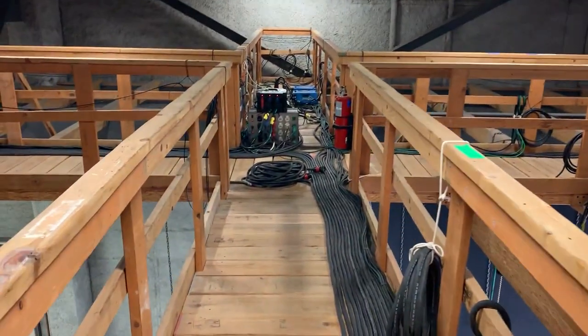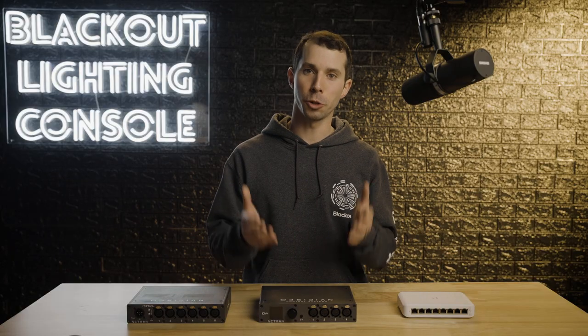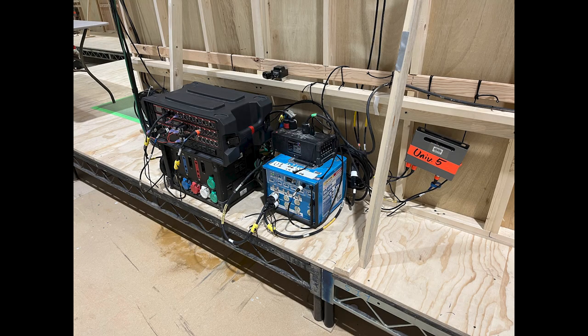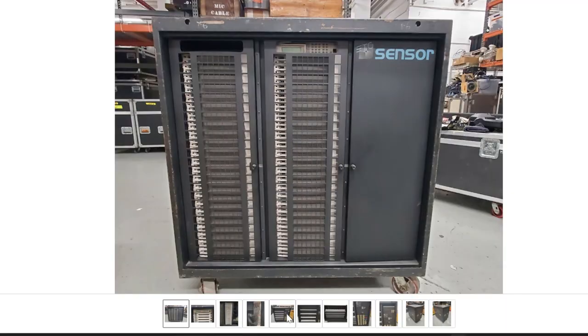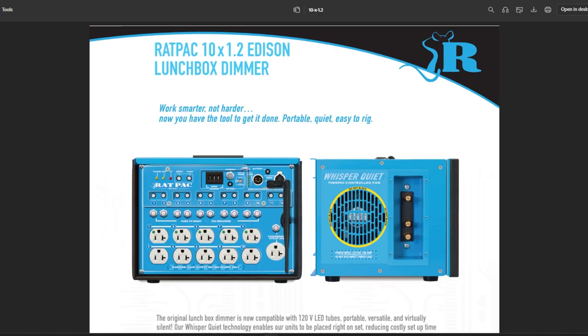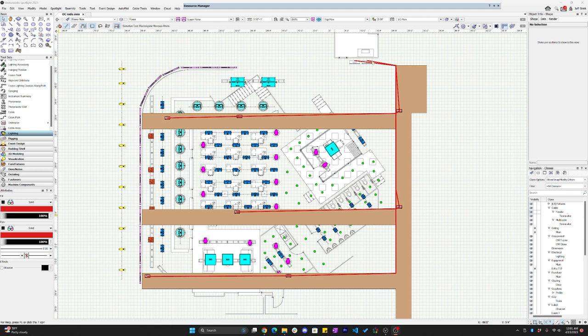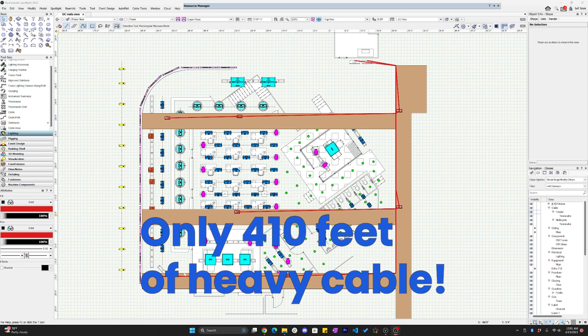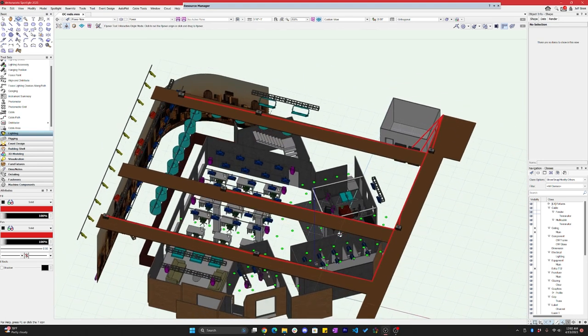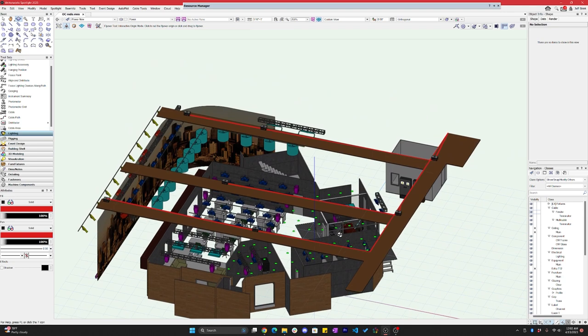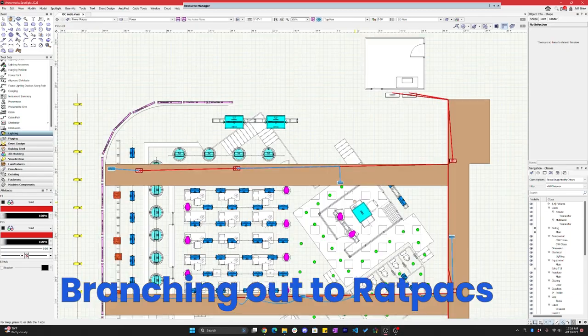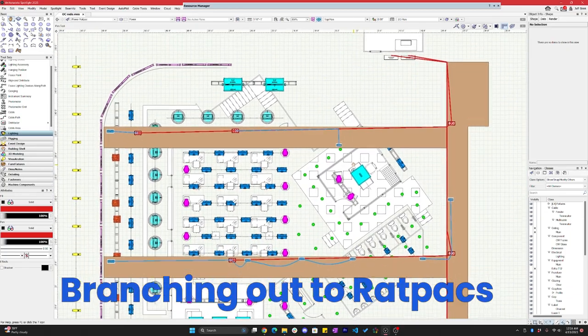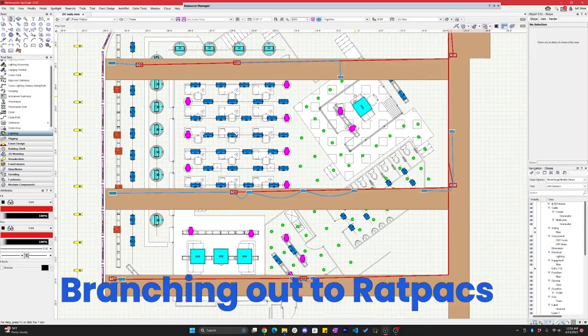The other way, which is how a lot of sets rig now, is that you run your 2-0 and 4-0 to the set, where you branch out to little dimmers scattered around set. Instead of the big touring dimmer racks, you have rat packs. The dimmers are right on set, and the only reason this can work is that they are silent. Rat packs and LEDs have kind of revolutionized how we typically lay out power infrastructure on today's sets. I would have my main trunk of cable going to the center of set here up in the catwalk and then branch out on the ground all around set.